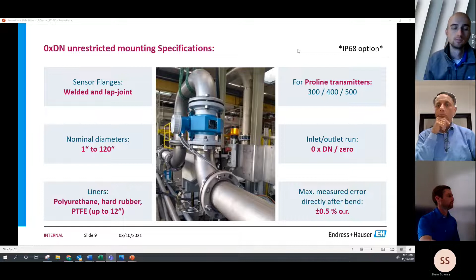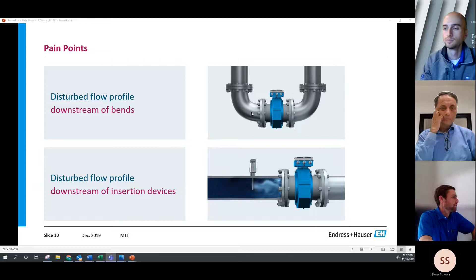So taking a look at some of the pain points that we're accustomed to when trying to retrofit applications or fit mag meters where generally they weren't allowed or they weren't installed and reading accurately. Pipe bends, very common, create a lot of vortices coming around these corners. Insertion devices, and sometimes you don't think about it, but buildup kind of has the same effect as an insertion device. So if you have corrosion that's built up on the inside of the pipe, that can create turbulence as well. And if you're thinking long term, down the road, corrosion may not be here day one, but corrosion, of course, builds up over time. So forward thinking, if it is a service that is going to be subject to corrosion, something to keep in mind, how that flow profile is going to change over time.